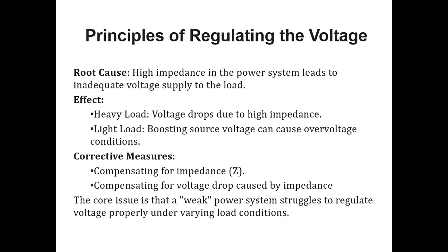Now why does this happen, and what is the reason behind it? If you think about the root cause, with heavy load there is a voltage drop due to high impedance, and with light load, boosting the source voltage can cause an overvoltage condition. High impedance means more load, heavy load, and then you get a voltage drop. Compared with that, light load means less load, and in that case you get an overvoltage condition, which in simple words is the voltage swell. So there is continuous deregulation of the voltage; regulated voltage is not there.